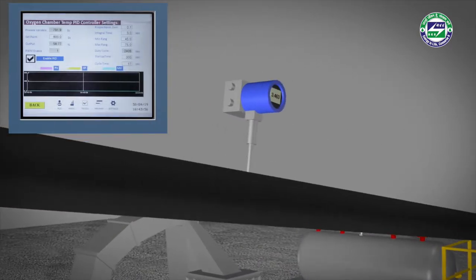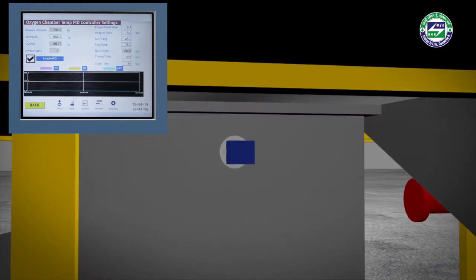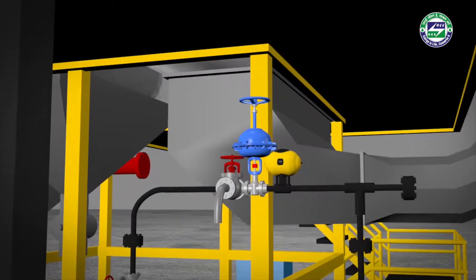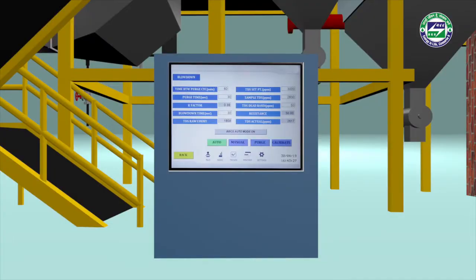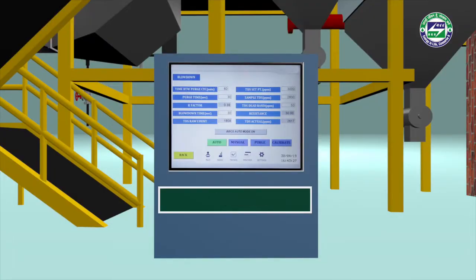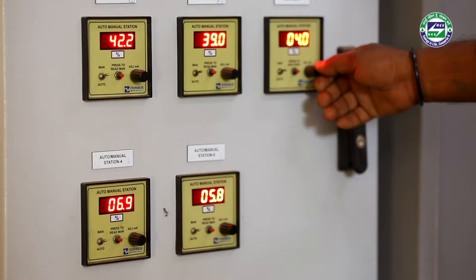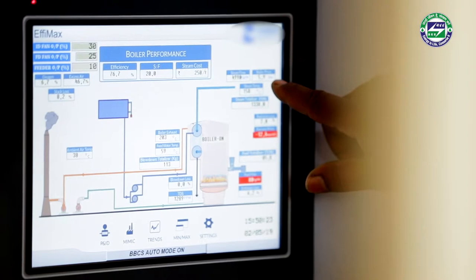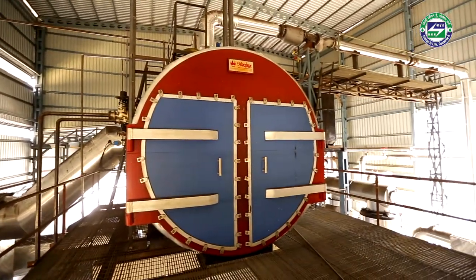The system also controls the forced draft based on stack oxygen and furnace draft pressure values at different loads in a synchronized manner. The advanced system controls blow down water automatically based on the TDS level of the boiler water, and also analyzes the blow down quantity and feed water temperature patterns. The technology changes operating parameters to arrest on-off losses by analyzing fluctuations in load patterns generated by the boiler system.